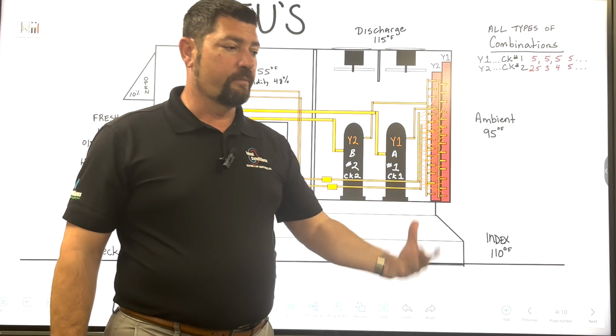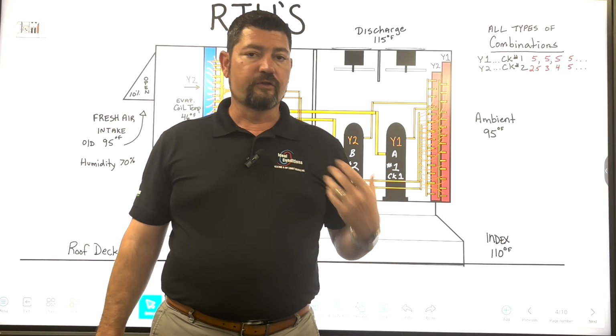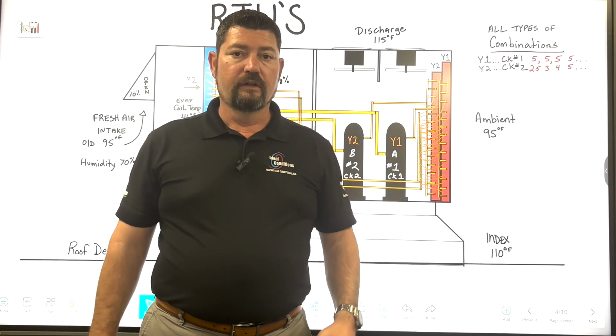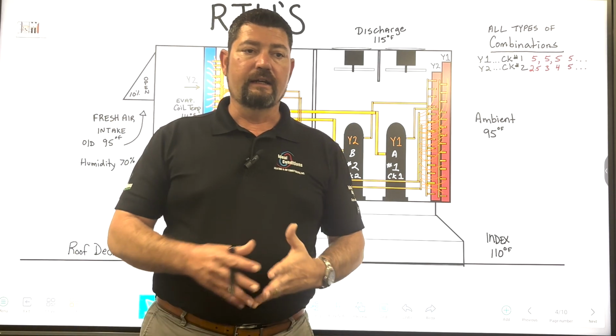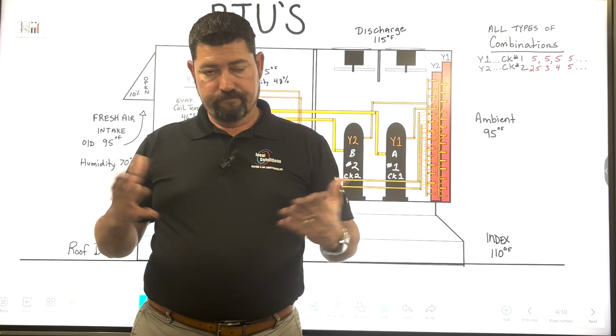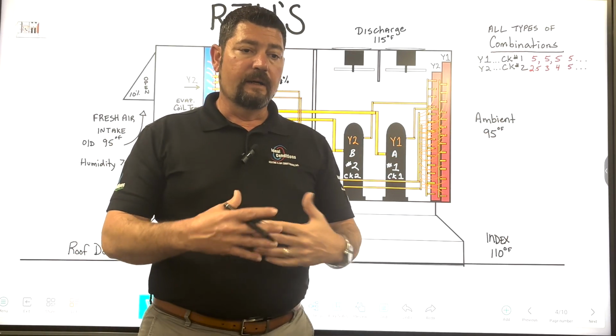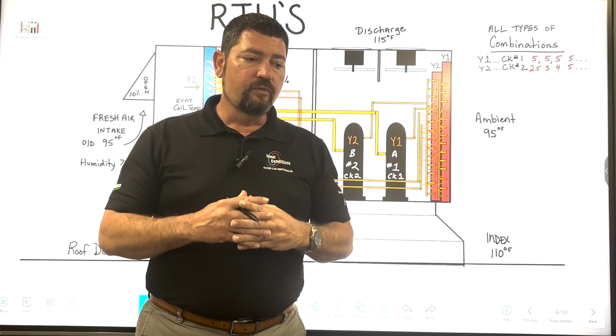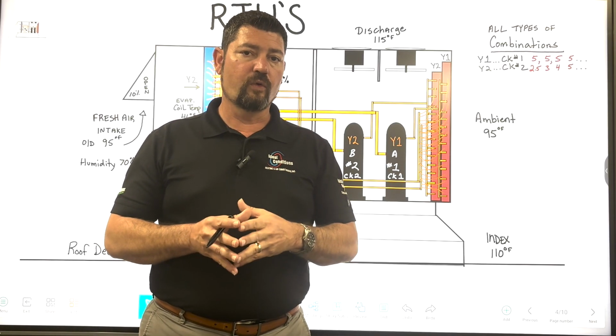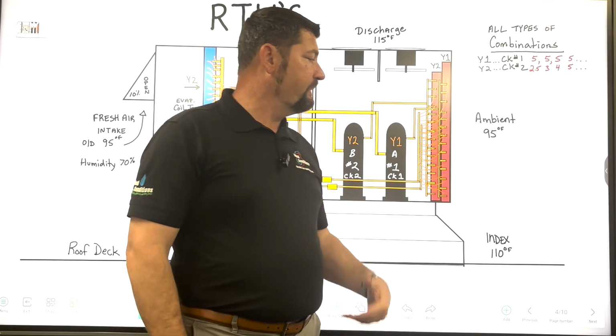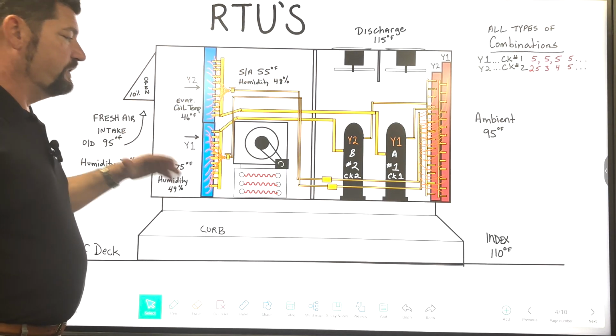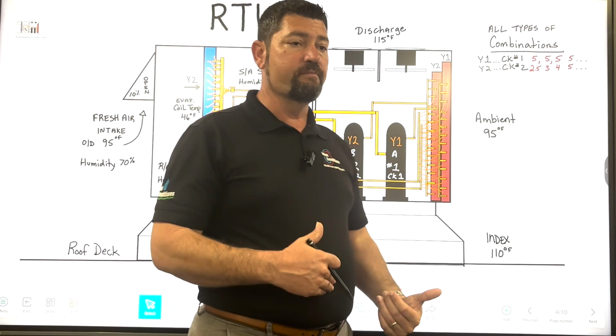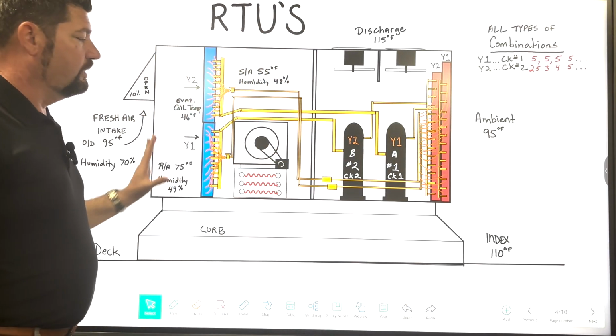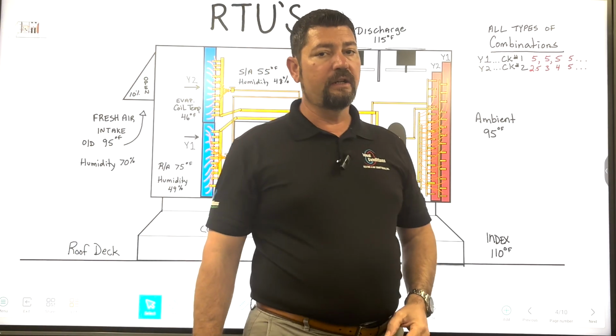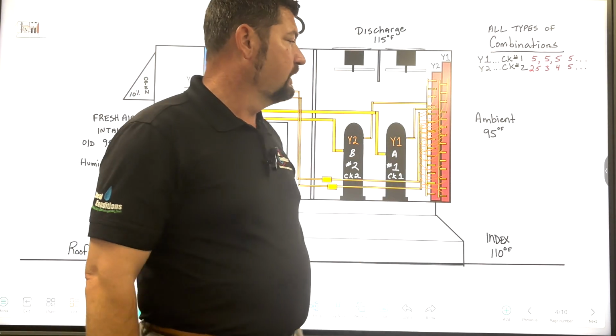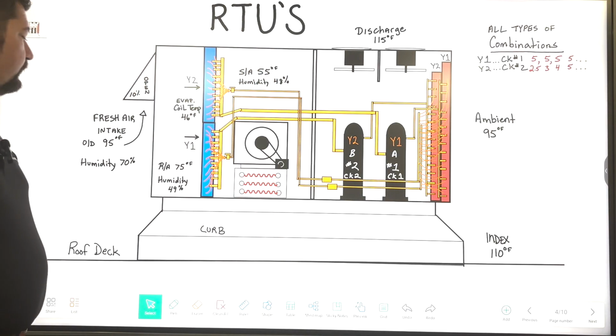They're commercial. They're built for a high heat load. If there's a low heat load, typically half the unit runs, half the unit's capacity, that is. And then it runs the other half of the capacity, or whichever combination you want to look at, right? When there's a higher heat load. So there's no direct concern or controls for dehumidification, right? And so that being said, they can only remove so much moisture. So you have to be very careful not to add moisture to the building or have these things running out of sequence. Rooftop package units are very known to get humidity in the building because things just are not done correctly. A lot of negative pressure is causing that as well.